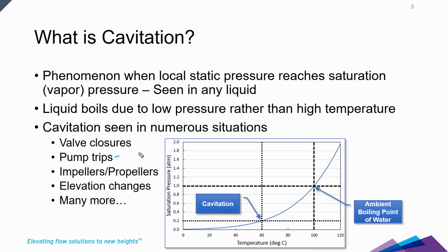Other times is if you have a pump trip event. Well, when your system pressures just drop because there's no more energy being added to your fluid, that will very quickly have the possibility to encounter cavitating behavior. You can potentially see cavitation happening on your pump impellers. That would be more so if you have NPSH problems. So if your NPSH available is not high enough than that which is required by your pump, then you're going to be cavitating inside your pump, and that's a bad situation.